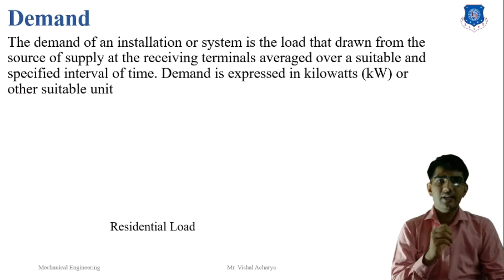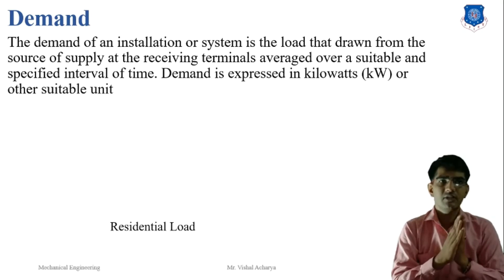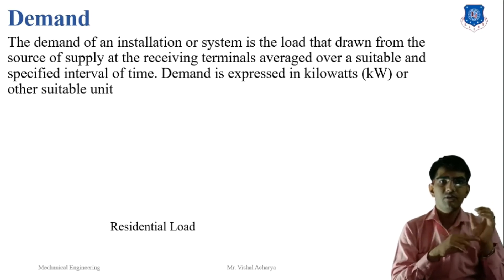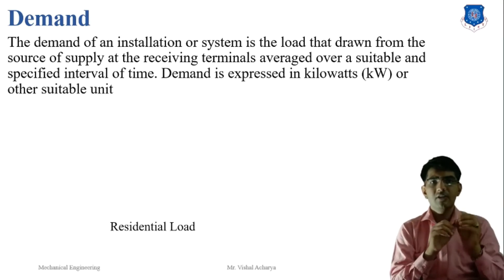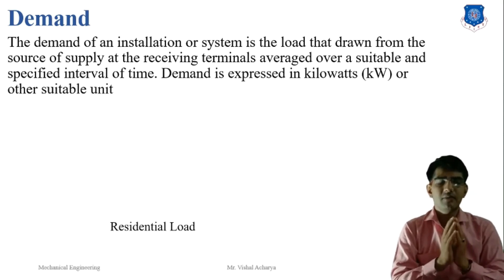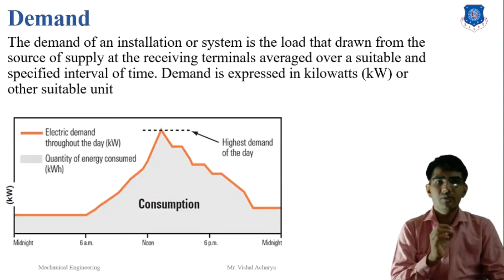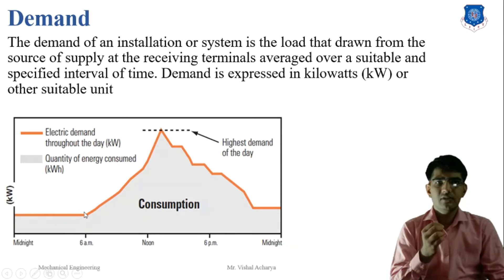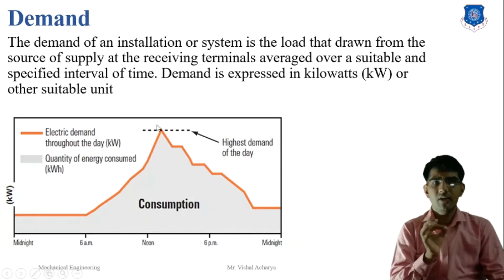The next term is demand. The demand of any installation or system is the load drawn from the source of supply at the receiving terminal, averaged over a suitable and specific period of time. Demand is expressed in kilowatts or other suitable units. For residential load, the highest demand throughout the day is called the peak load or peak demand.